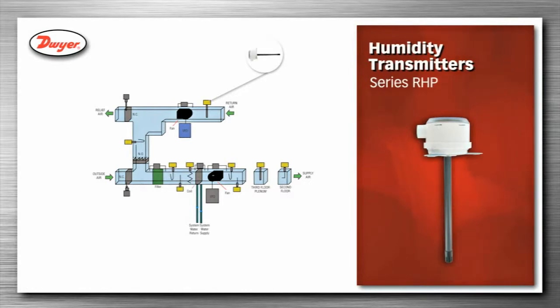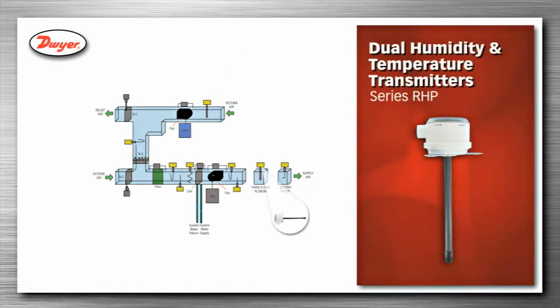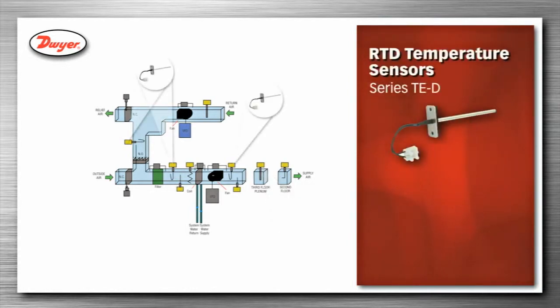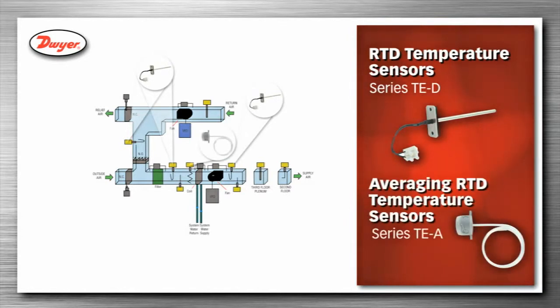Humidity transmitters, Series RHP, are inserted into the duct and used to monitor the zone discharge humidity. Dual humidity and temperature transmitters, Series RHP, are inserted into the duct and used to monitor the exhaust air humidity and temperature. Series TE-D RTD temperature sensors and Series TE-A averaging RTD temperature sensors are inserted into the duct and used to monitor the supply air, mix air, and exhaust air temperatures.